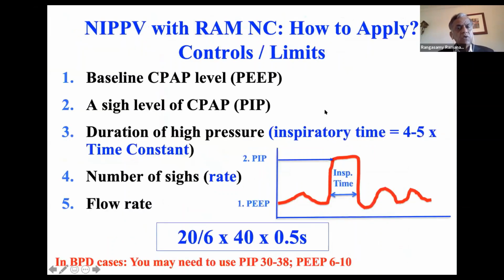So it's a rule of thumb. If I'm setting with a RAM cannula or any other interface, if I set 20 PIP, the baby is not getting 20 PIP. The baby will get about 15 to 16 at the hypopharyngeal level. No one knows what the pressure is at the lung level because it's not easy to measure pleural pressures to get a good idea. So how do we do that?